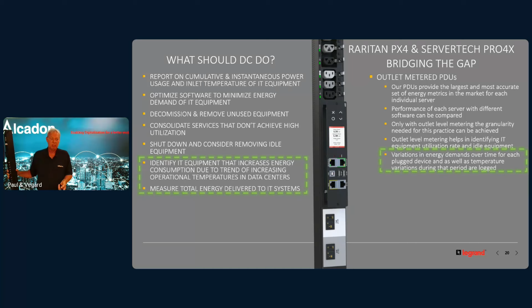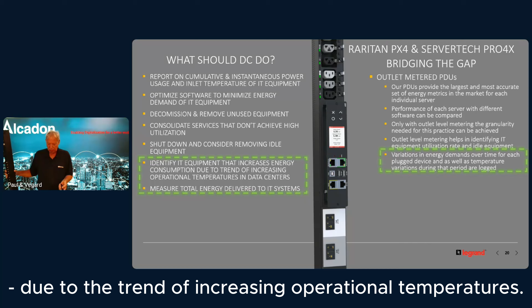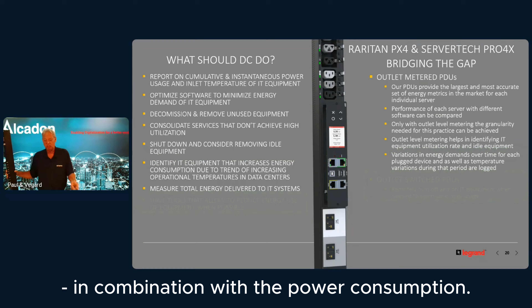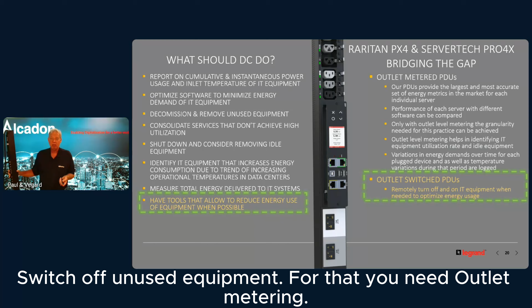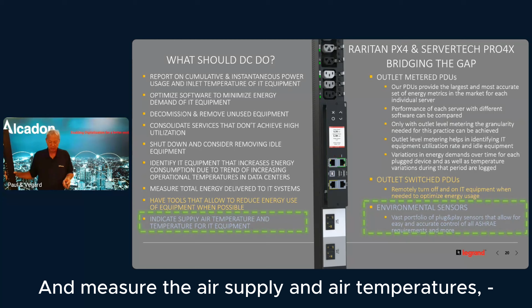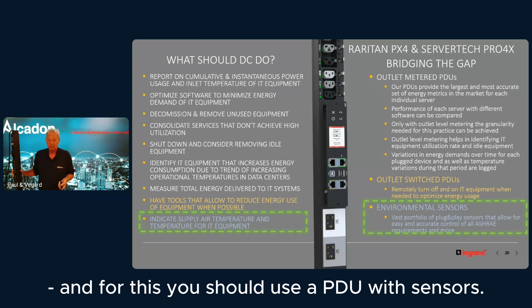Okay, you can see which equipment is in use and which equipment is not in use by measuring at the outlet level. Identify equipment that has increased energy consumption due to the trend of increasing operational temperatures. That has to do with temperatures, of course, in combination with the power consumption. Switch off unused equipment. For that, you need outlet metering. And, of course, measure the air supply and air temperatures. And for this, you should use a PDU with sensors.